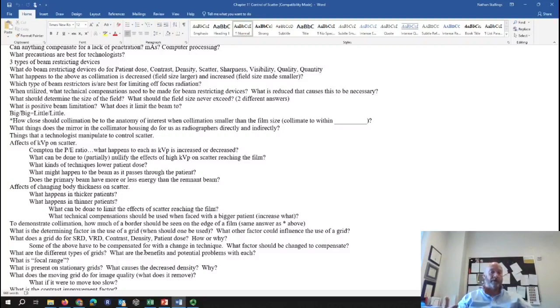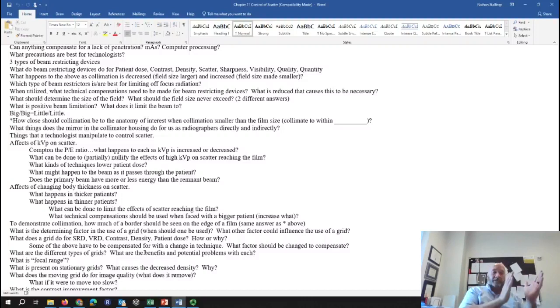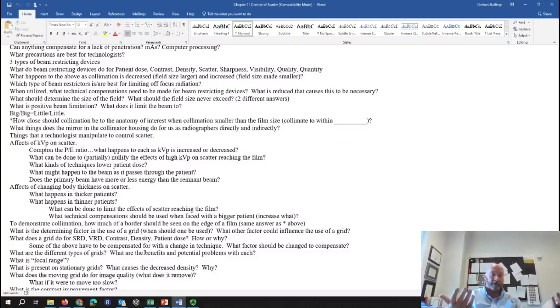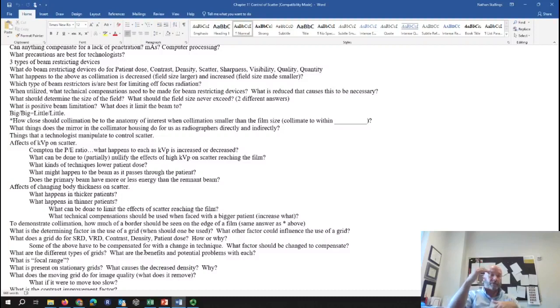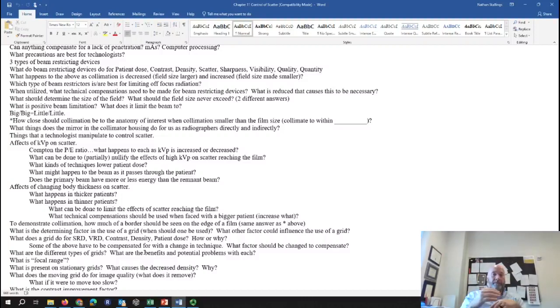Different terms for grid positioning errors: off-level means the grid is tilted, equivalent to angling against the grid strips. Off-center means you're not centered to the middle of a focused grid. Inverted grid means the focused grid is upside down. A parallel grid doesn't matter if it's inverted. Off-focus means the SID is wrong. Off-center means you're not centered to the center of the grid laterally — longitudinally it doesn't really matter, but laterally it does.